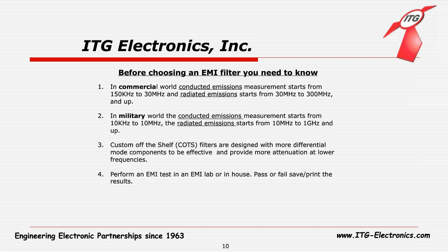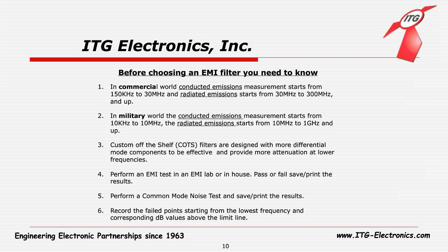Again, if possible, perform an EMI test in an EMI lab or in-house, and pass or fail, save and print the test results. Perform a common mode noise test and, again, save and print the test results. Record the fail points starting from the lowest frequency and the corresponding dB value above the limit line.